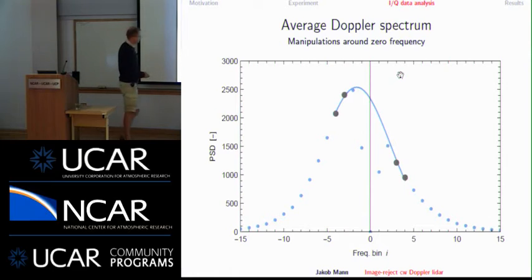Then this is the average of all spectra. It looks very nice except around 0. At 0 frequency we have no signal. We cannot detect things that are not moving. And at the 2 frequencies close to 0, we also underestimate the spectral energy. So before we go on and determine the Doppler frequency, we interpolate between these points to get a more reasonable spectrum.